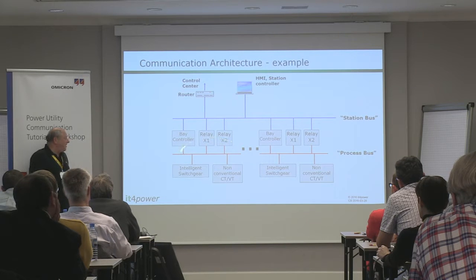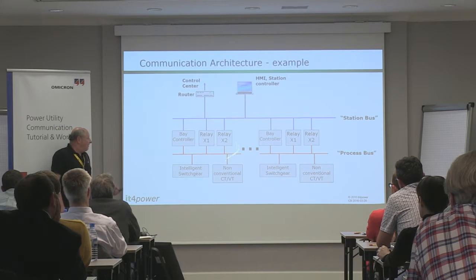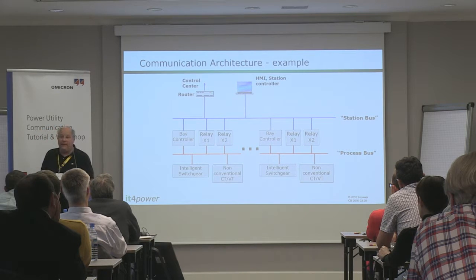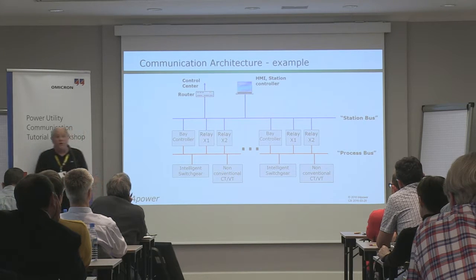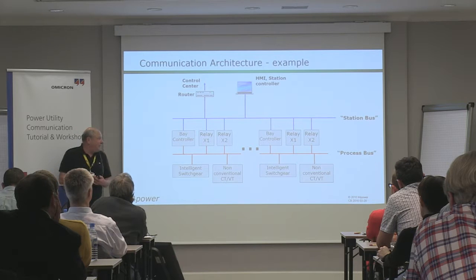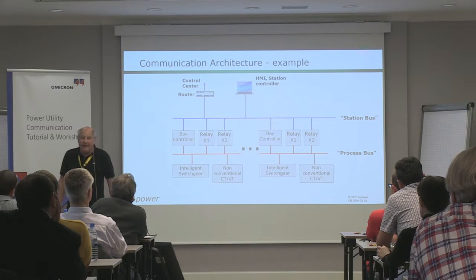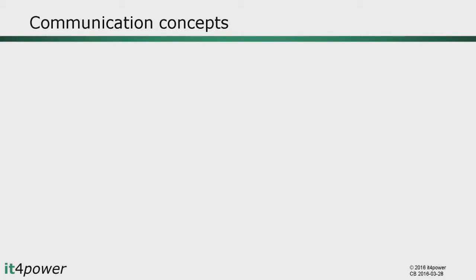New with 61850 was the addition of a process bus — a digital interface going further down into the process, enabling intelligent switchgear to support a communication interface directly. It supports non-conventional CT/VTs but also conventional CTs with standalone merging units, so that analog-to-digital conversion happens down in the switchyard. In this picture the station bus and process bus are shown as two independent networks, but 61850 is open on that — it allows all kinds of communication network topologies.